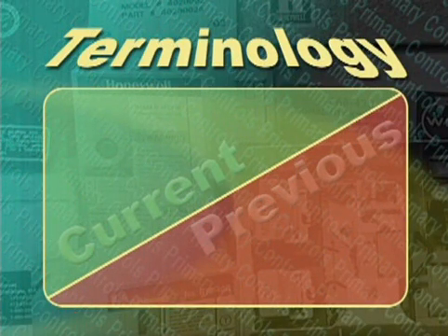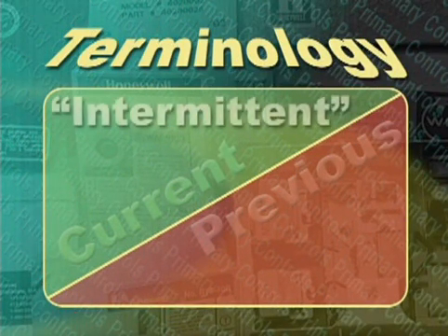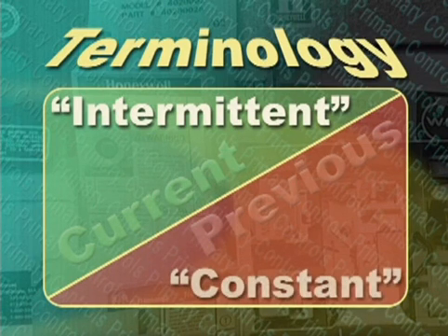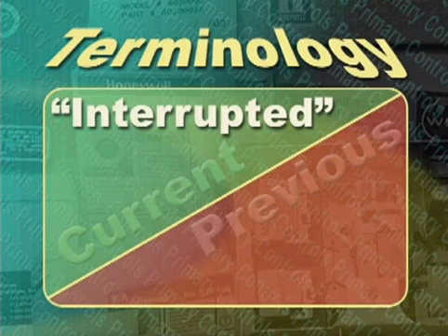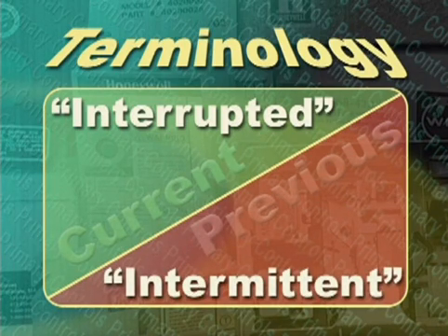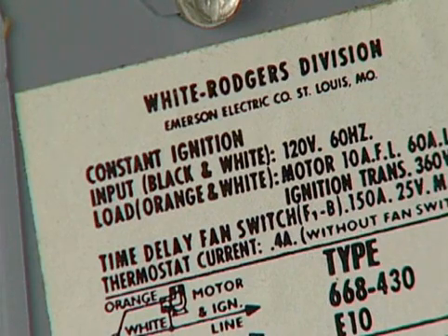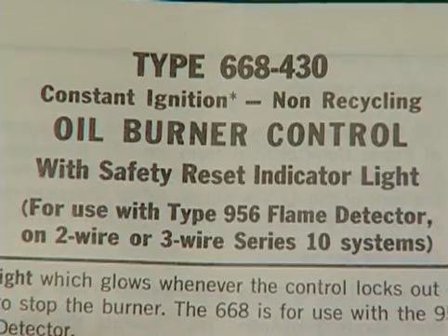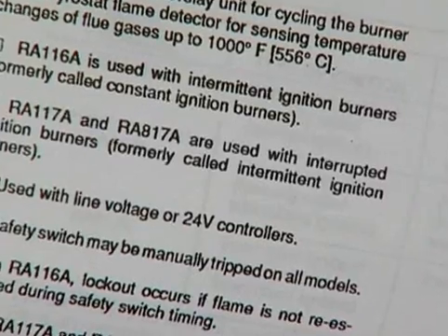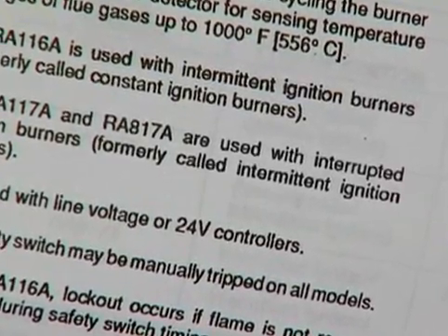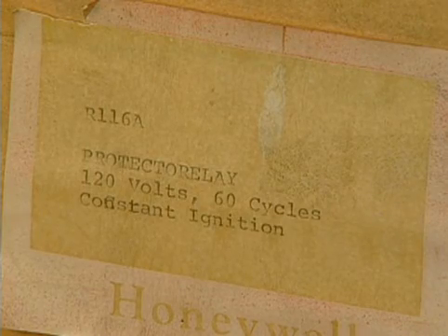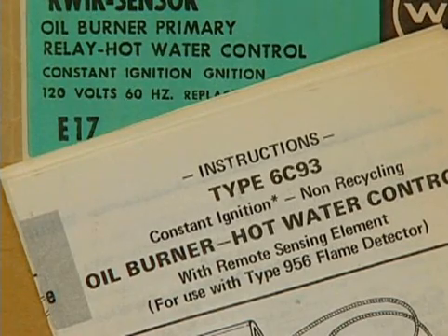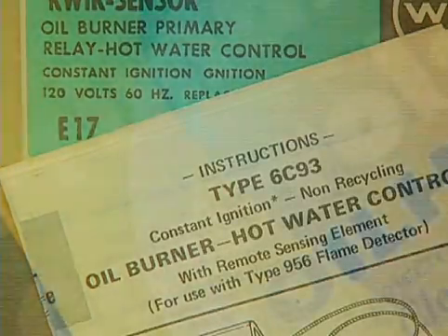Through a confusing evolution of terminology, what we now call intermittent was formerly called constant duty ignition, and what we now call interrupted was formerly called intermittent duty. It's important that you understand these differences because you may encounter primary controls in the field which are labeled according to the old system, and may even receive replacement controls from older stock which use the old nomenclature.